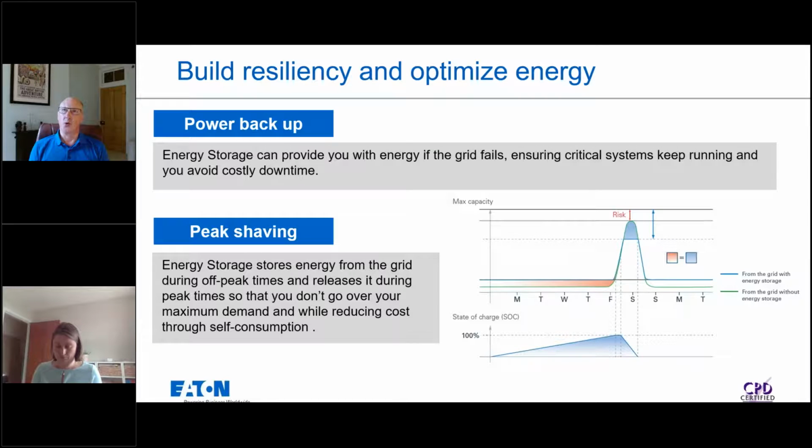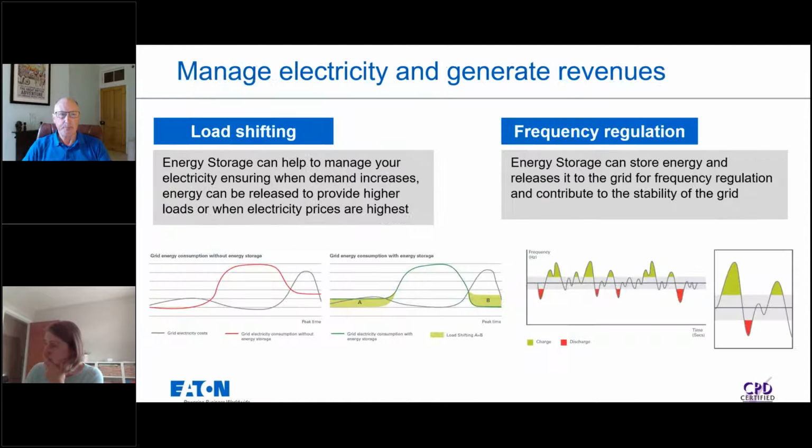They had a model store demand of over 300 kVA during the entire daytime trading hours. It's actually a 24-hour store, this, but overnight demand was much lower. So we could charge a battery overnight and use that additional energy then to support that gap between the 250 kVA supply and a 300 kVA demand during those trading hours. And that alone was the business case for the battery energy storage. We're also doing some solar self-consumption there as well now, but that wasn't part of the original business case.